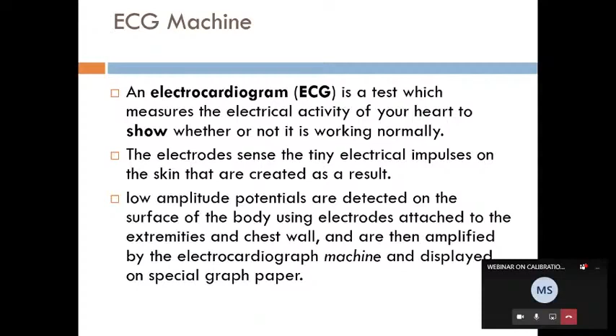ECG can be measured with tiny electrodes. The electrode picks up the signal, which is transferred to a cable, the ECG cable, and from the ECG cable it is connected to a module. In this module you have a preamplifier and amplifier; everything is inside the machine. Next picture: this is a typical ECG machine.